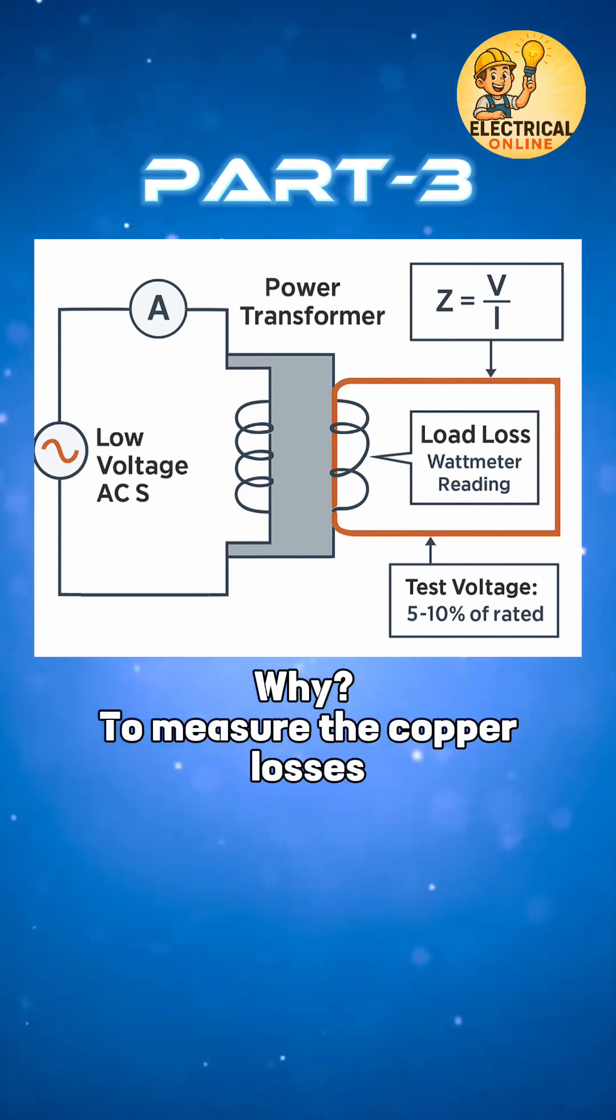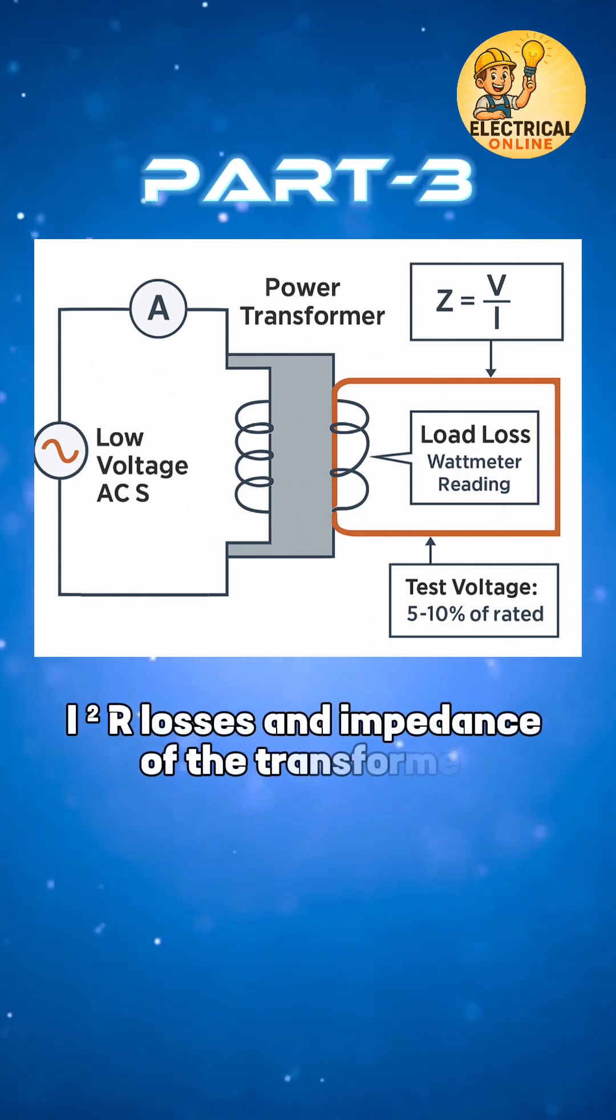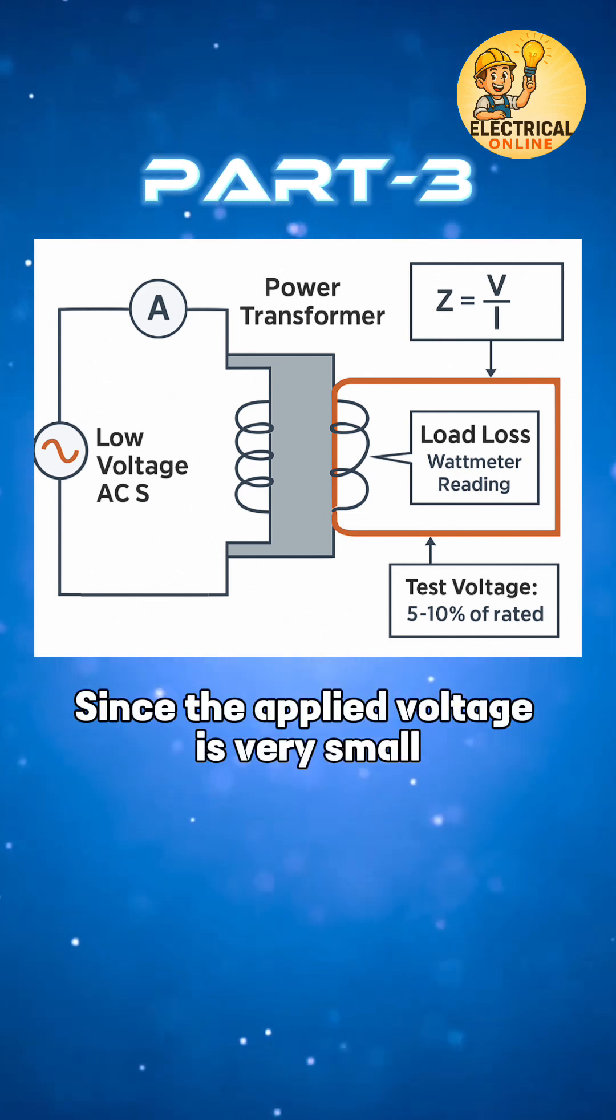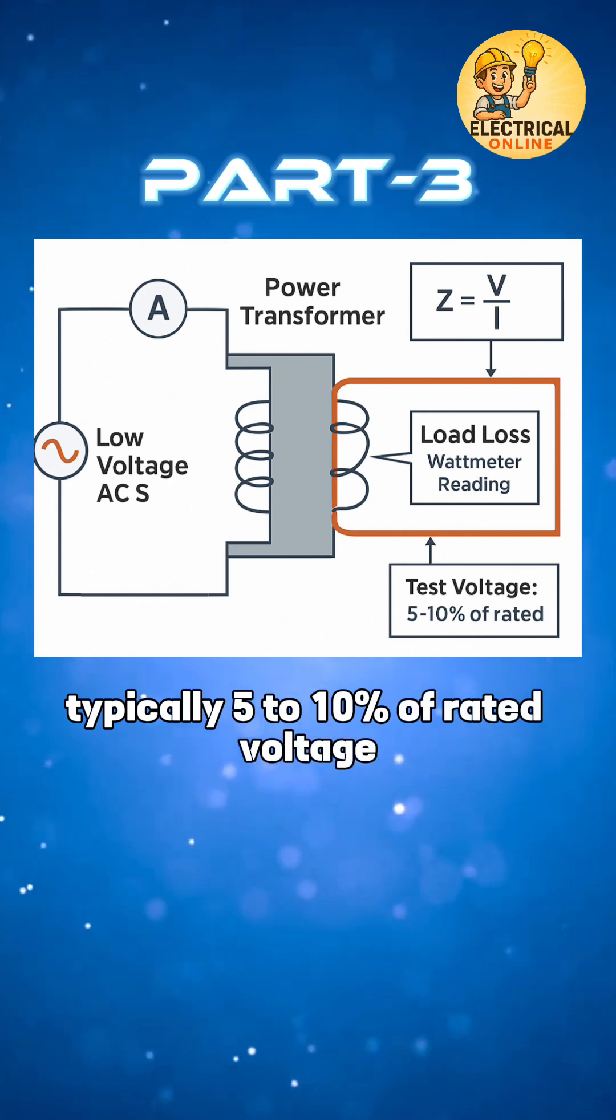Why? To measure the copper losses, I squared R losses, and impedance of the transformer, without the core playing a big role, since the applied voltage is very small, typically 5 to 10% of rated voltage.